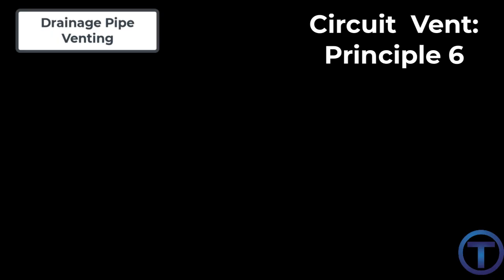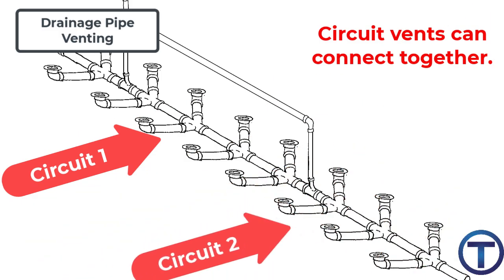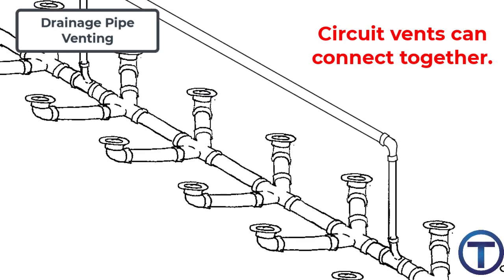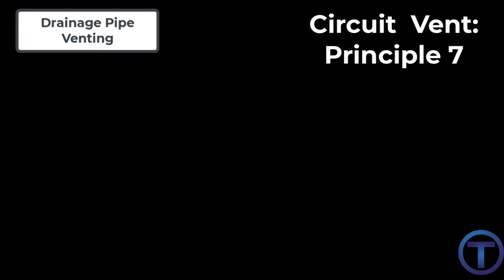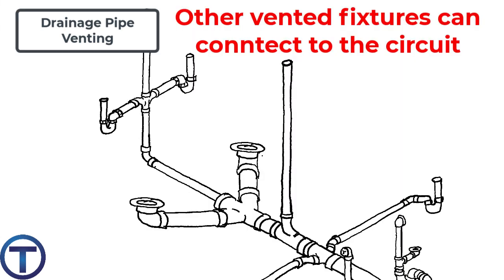Circuit vent principle six: circuit vents are allowed to be connected together. Every eight fixtures is considered a circuit, and they can continue in one line with multiple circuit vents. Circuit vent principle seven: fixtures other than the circuit vented fixtures are allowed to connect to the circuit, provided that they are either individually or commonly vented. This is also different from wet venting, which is very exclusive to bathroom group fixtures.